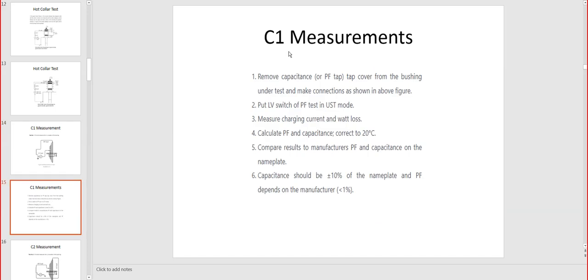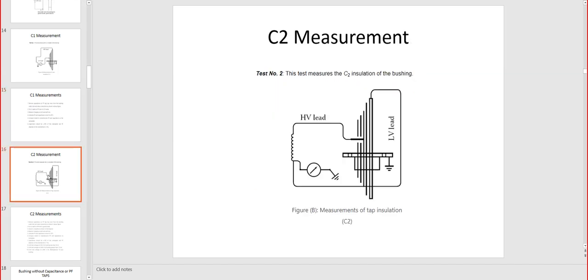And the procedure to do this collar test: remove the capacitance of the tap cover, low voltage switch on, the power factor test on UST mode, measuring charging current and loss watt, calculate power factor and capacitance at 20 degrees as we said, compare results with manufacturer power factor and capacitance on the nameplate. Pay attention, the capacitance that we read should be within plus or minus 10% of the nameplate of the manufacturer. And yes, sometimes they allow for variation, but not more than 10%. And power factor depends on the manufacturer. Sometimes the change they allow is less than 1%.